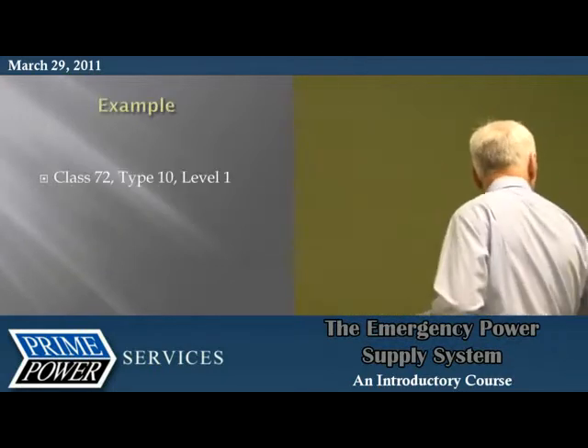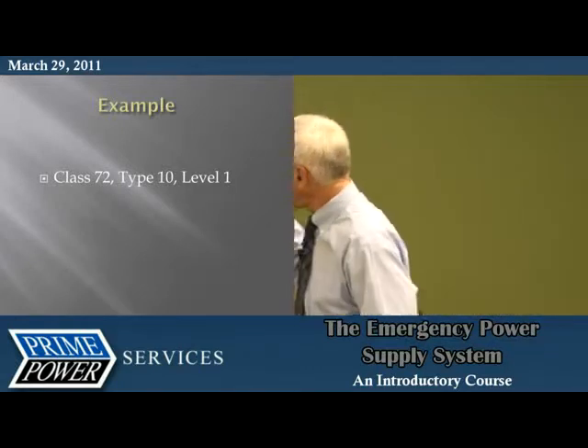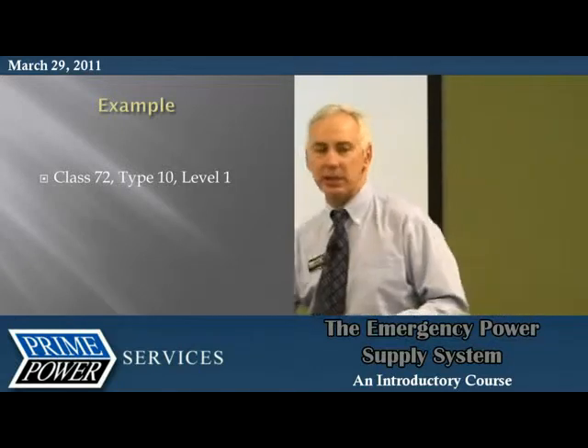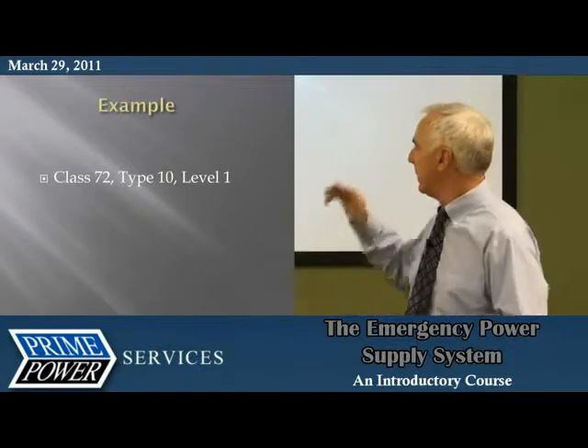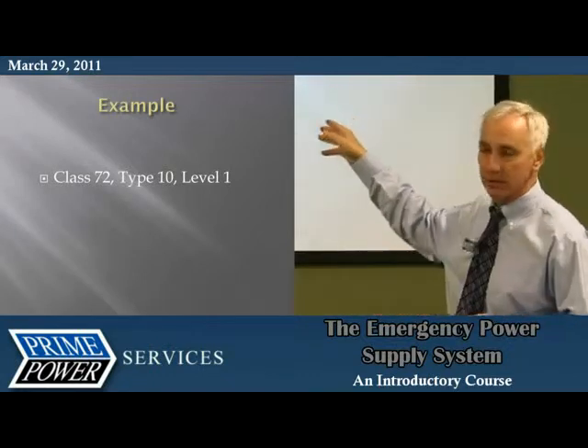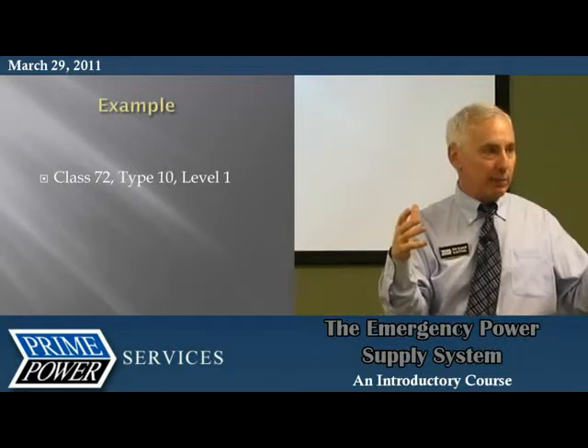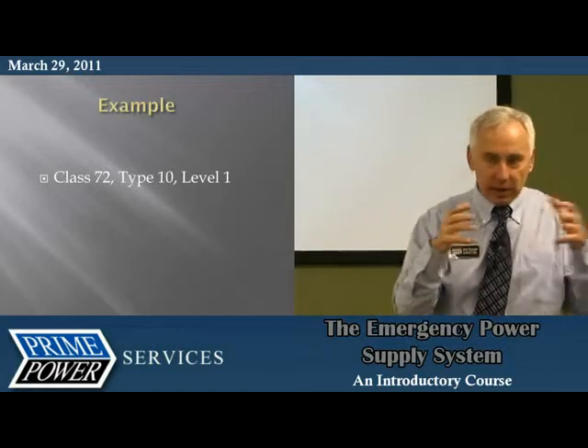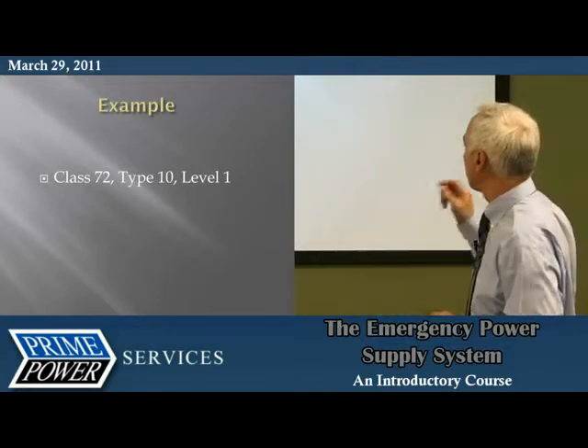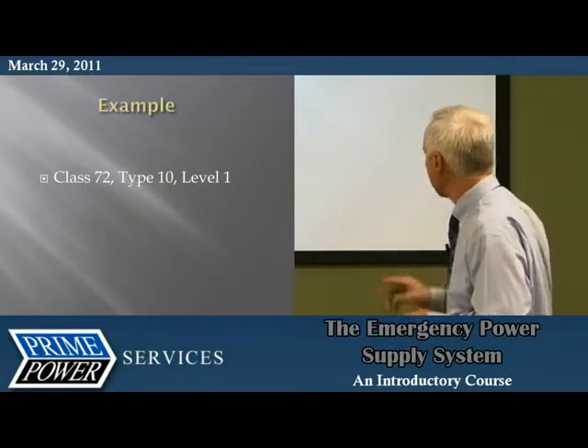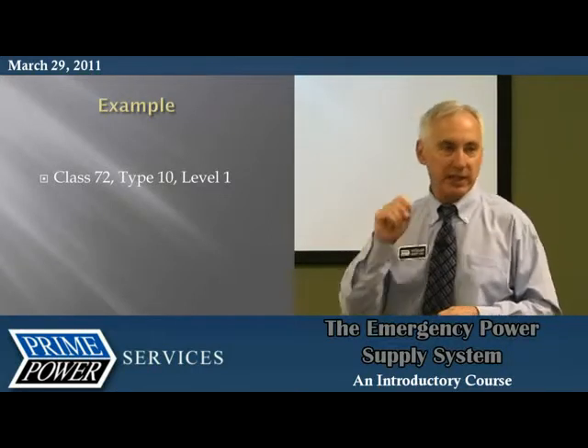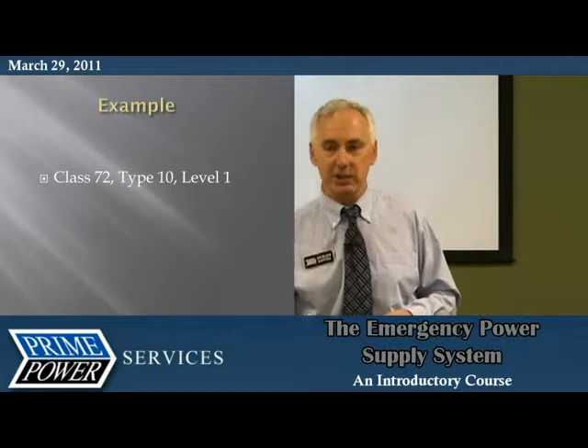That defines the level. So just an example here: Class 72, this is a typical hospital classification. It has to run for 72 hours in what they call an island mode, so it could be totally self-contained for 72 hours. It has to be online in 10 seconds, and it's level 1, which means that if it doesn't work, people could get injured.